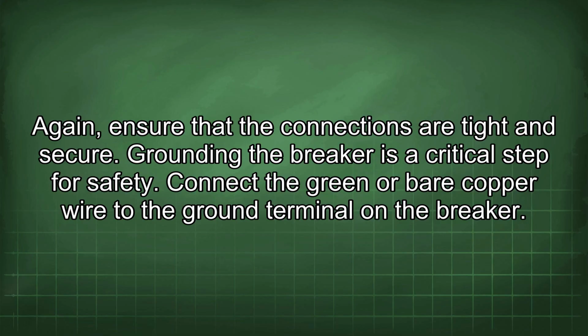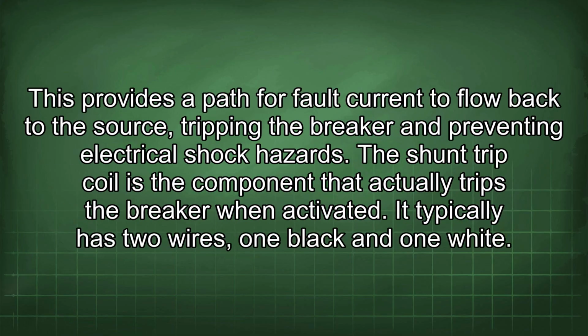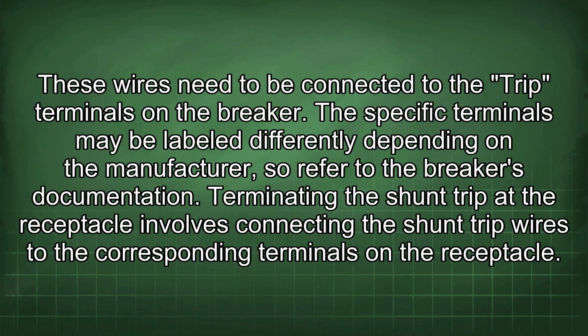Grounding the breaker is a critical step for safety. Connect the green or bare copper wire to the ground terminal on the breaker. This provides a path for fault current to flow back to the source, tripping the breaker and preventing electrical shock hazards. The shunt trip coil is the component that actually trips the breaker when activated. It typically has two wires, one black and one white. These wires need to be connected to the trip terminals on the breaker. The specific terminals may be labeled differently depending on the manufacturer, so refer to the breaker's documentation.